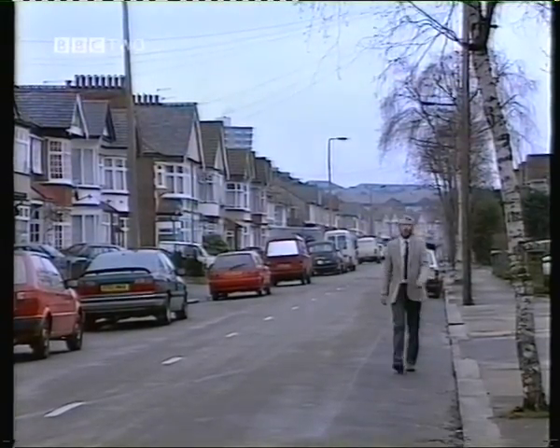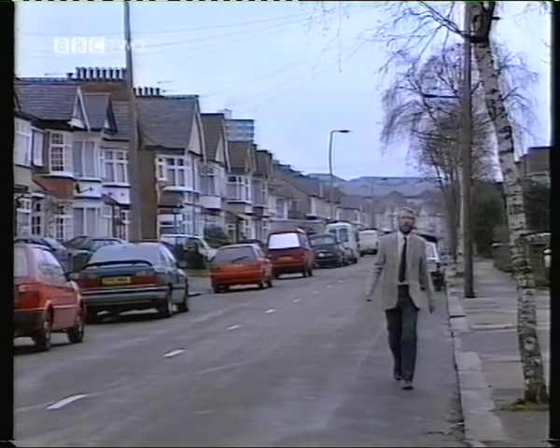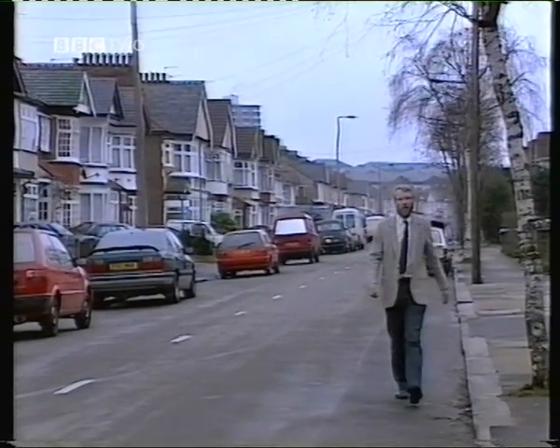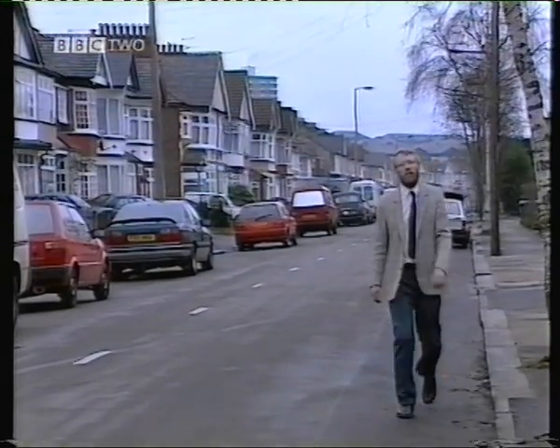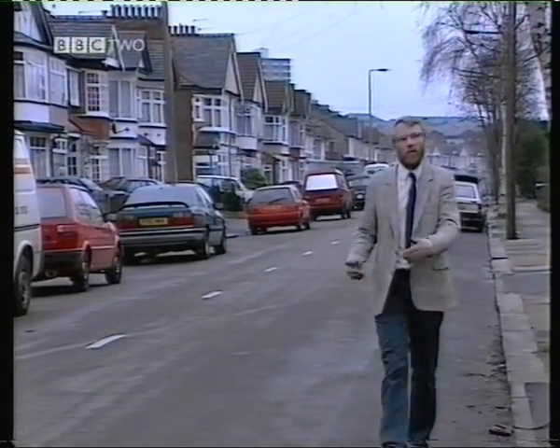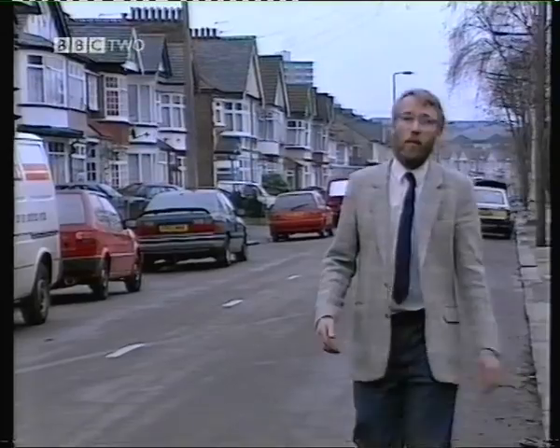So you put the cable into the trench and fill it up again. But you only get a fixed amount of cable on a roll, something like the length of this street in fact. And then you've got to joint two cables. And remember, this is an oil-filled cable, so it's a good bit more complicated than, say, joining an extension lead.